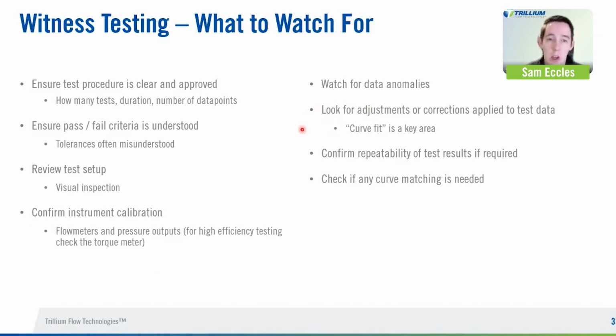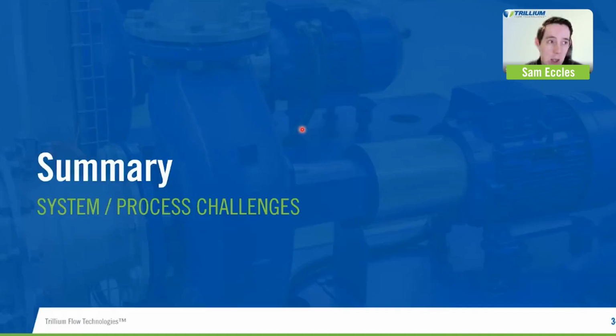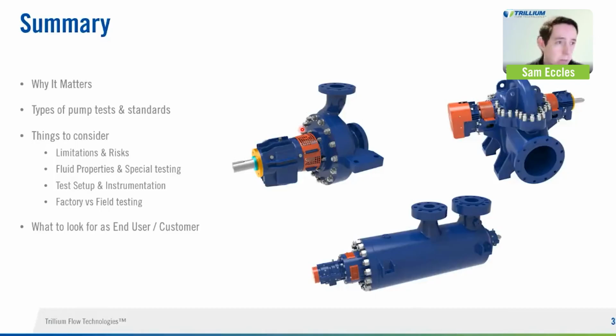So what you see in the curves that we've shown all the way through are a line of best fit, and that is what the pass or fail criteria is aligned to. But you want to see the raw data against that aligned curve. You want to make sure that no one's taking liberties with how that curve fit has been done. And that is a very, very key part of the process.